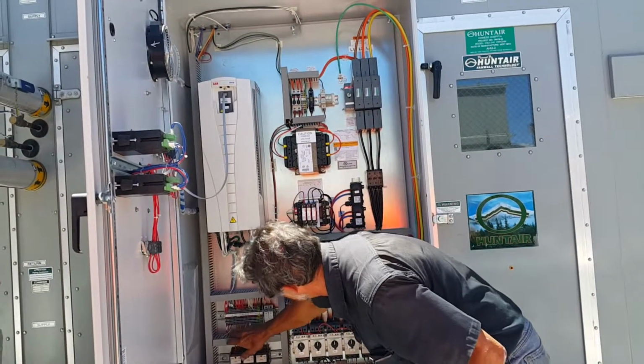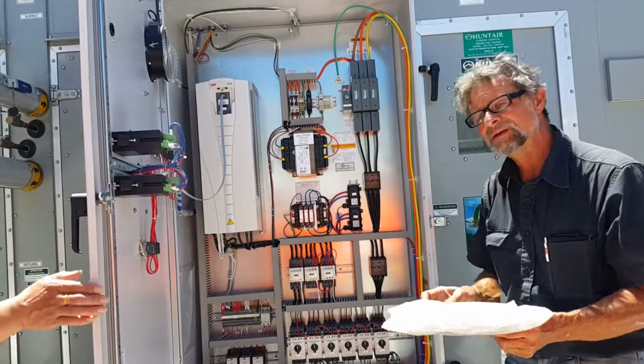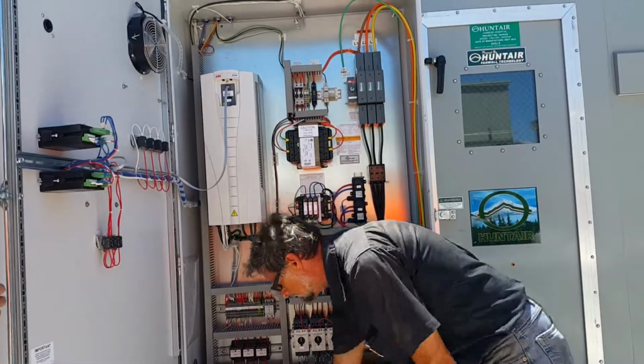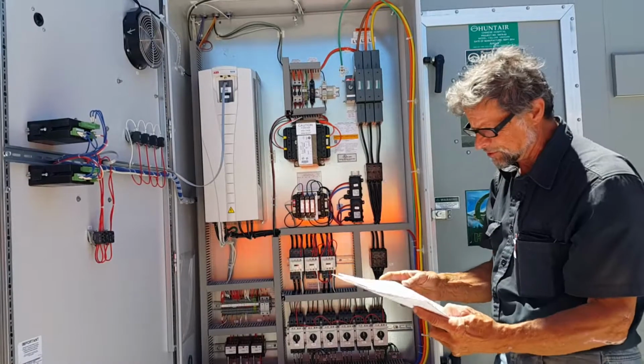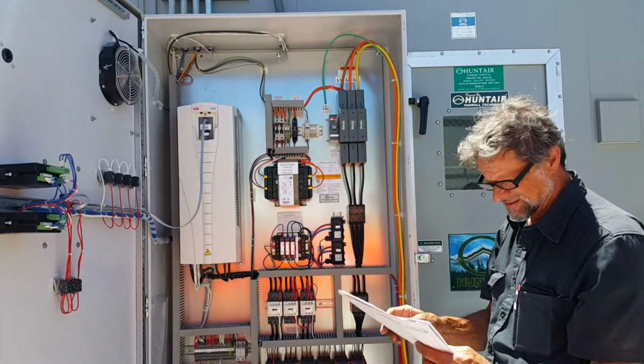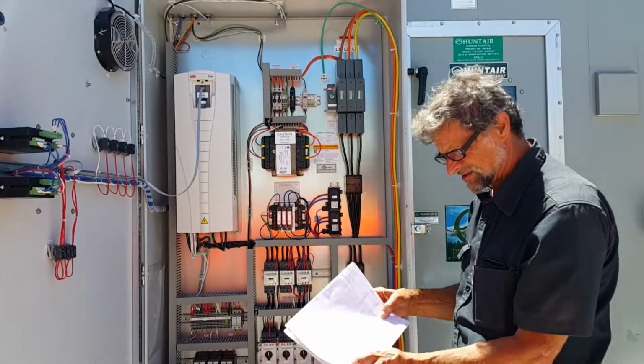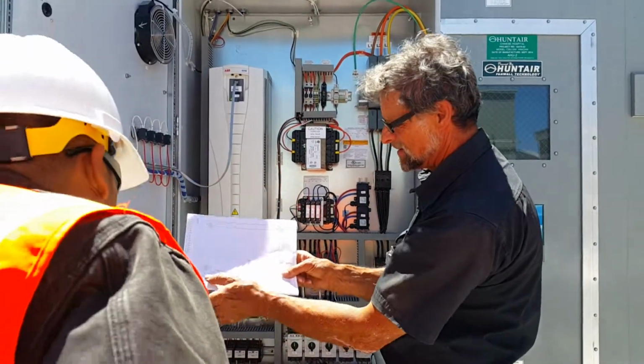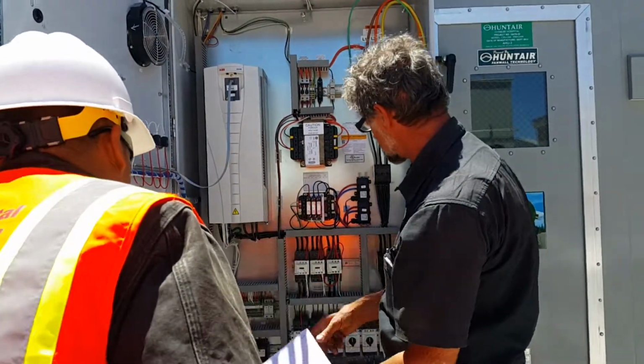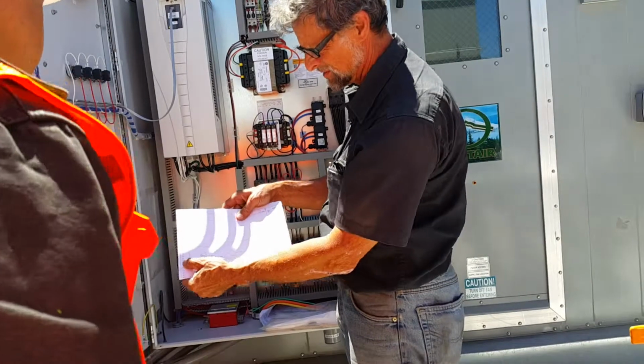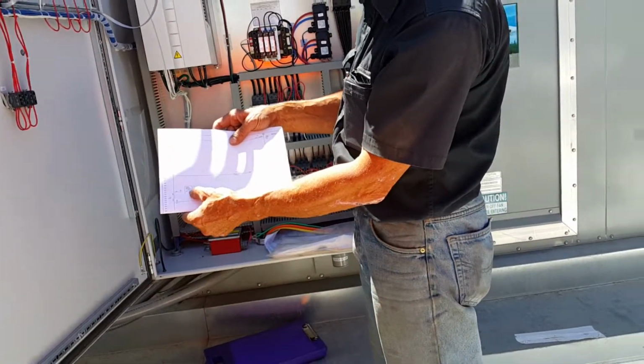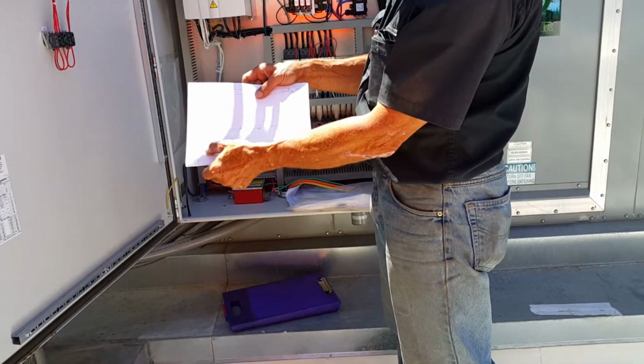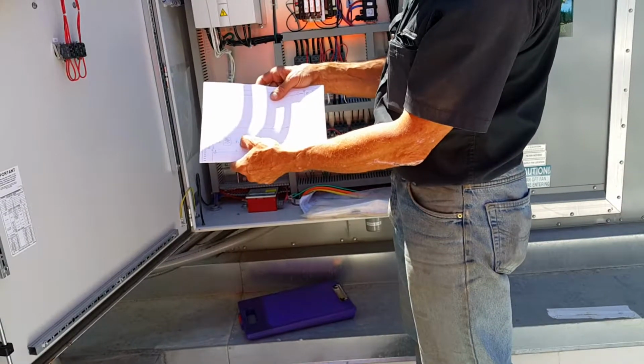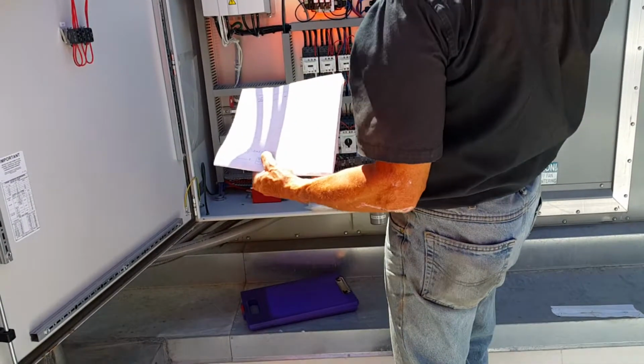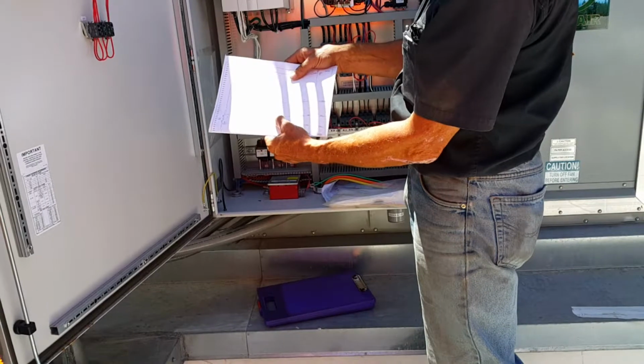So you have to do it through the BMS and this as well? Well, you can, if that system's down and you really need to get to it, the safety contact is here. See, there's a 110 volt circuit for all the controls in here. You come down here and the first line goes up to the safety circuit, normally open. And then you can add other safeties. Looks like you have a door switch on this as well. If you open the door, it shuts it down.